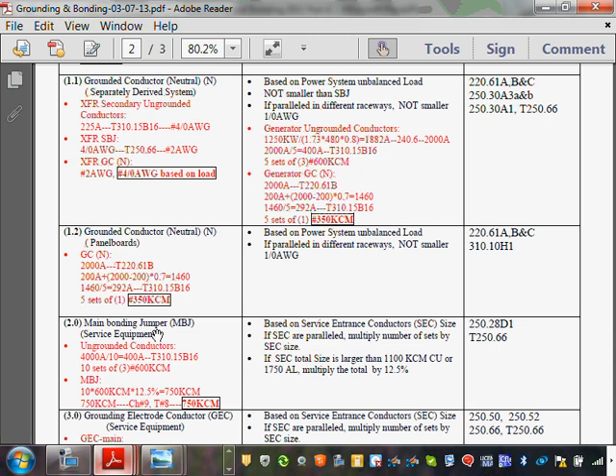So how do you size that baby? You size it based on 250.66 on the service conductor. If you exceed 1100 kcmil copper, then you have to take 12.5% of the kcmil size of the feeders coming to your building. So here's what I did. Ungrounded conductors, I have a 4000 amp switchgear divided by 10, give you 400. Go to 310.15(B)(16), and that will get you 10 sets of 600 kcmil.